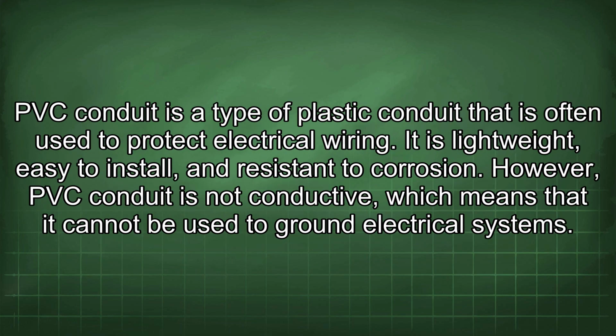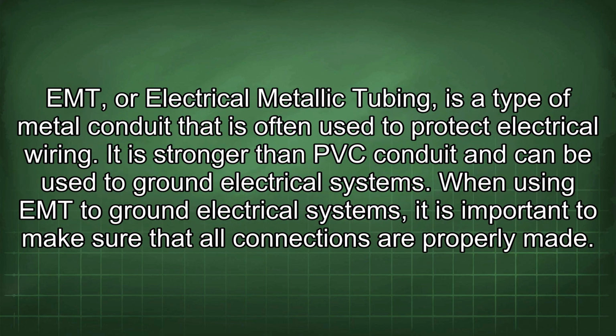PVC conduit is a type of plastic conduit that is often used to protect electrical wiring. It is lightweight, easy to install, and resistant to corrosion. However, PVC conduit is not conductive, which means that it cannot be used to ground electrical systems. EMT, or electrical metallic tubing, is a type of metal conduit that is often used to protect electrical wiring. It is stronger than PVC conduit and can be used to ground electrical systems.